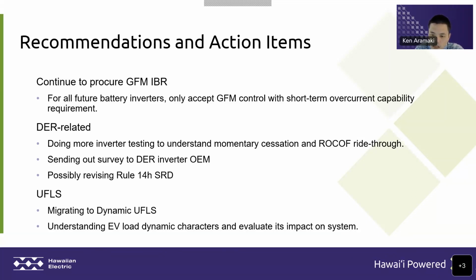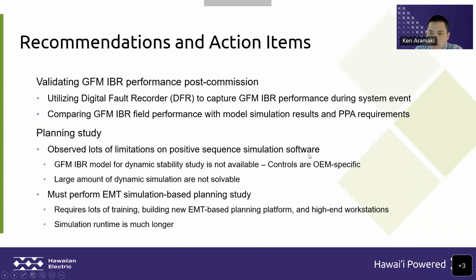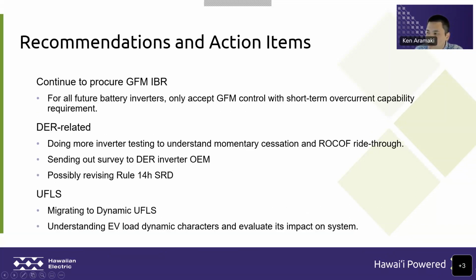And just like when NEM was growing at exponential rates, the requirements for our system are going to continue to be higher than the minimums being set within the standards. Also regarding under frequency load shedding, DER is generally interconnected to the distribution system, and it makes it difficult to maintain the effectiveness of the current UFLS scheme.